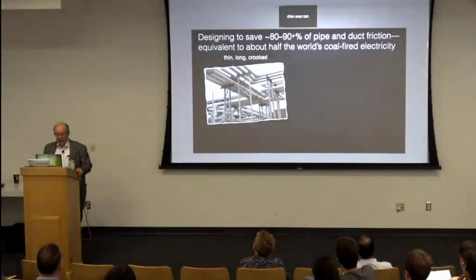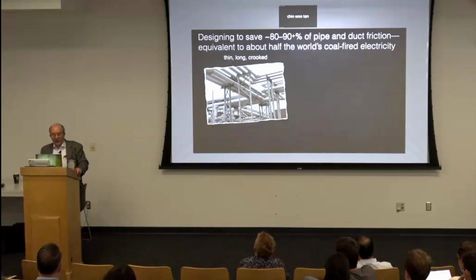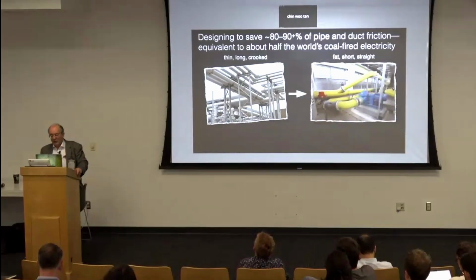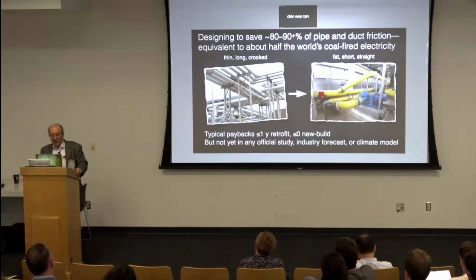Next, what can we do inside factories that make this stuff? Half the world's electricity runs motors, half the motor torque runs pumps and fans. Engineers focus on those devices' efficiency, but often forget that better pipe and duct design can save 80 to 90+% of the friction, 97% in my house. If everyone did that, it could save roughly a fifth of the world's electricity, or half the coal-fired electricity, typically paying back in less than a year in industrial retrofits and instantly in new builds.